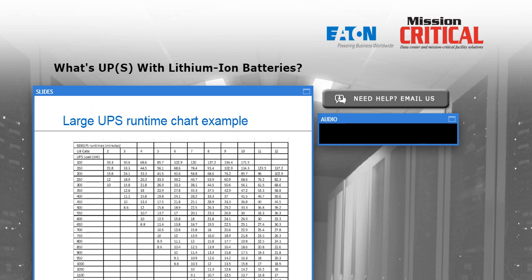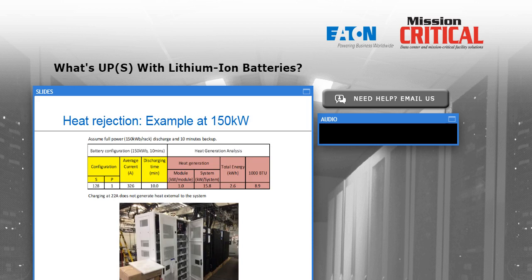Here's another example of a larger UPS system, say a 1 megawatt UPS with 12 battery cabinets in parallel, 12 strings in parallel, looking at 19 or 20 minutes of backup time. We can go longer than that, but we do have physical limits typically as to how many cables we can pull in to the UPS system or to a junction box. So again, consult with your UPS vendor. We have lots of flexibility and can usually meet your backup time needs for a very reasonable price.